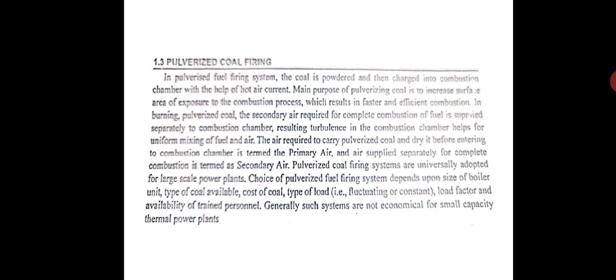For large scale power plants, this lump system or these stokers will not work, because they are only meant for small plants, as I said, for sugar industries with 10 to 20, 30 megawatt plants. But large steam power plants nowadays, around 500 megawatt or 650 megawatt each, all work on pulverized coal systems. The pulverized firing system depends on the boiler, type of coal, cost of coal, type of load, whether constant or fluctuating, load factor and availability of people. This kind of system is not suitable or economical for small power plants.